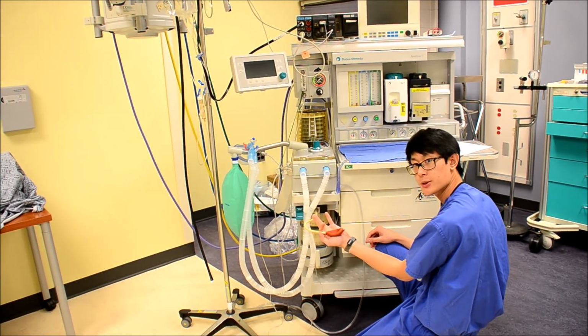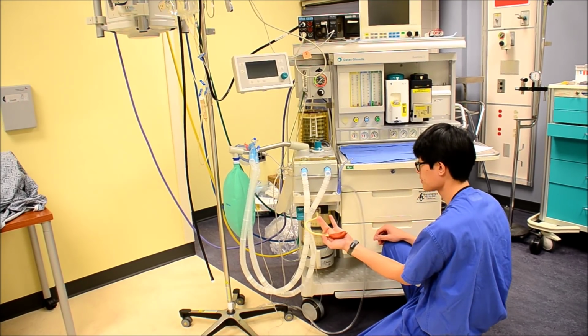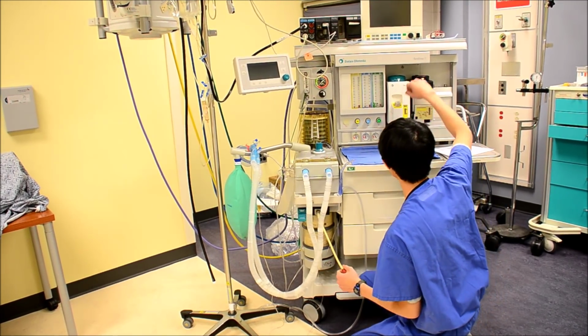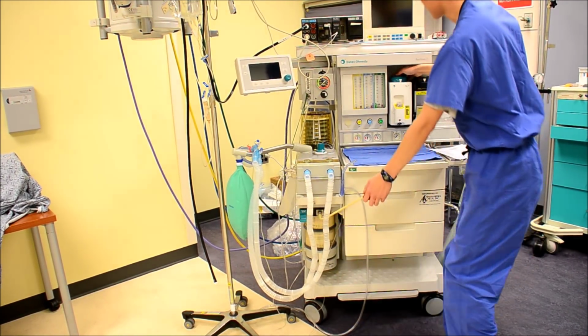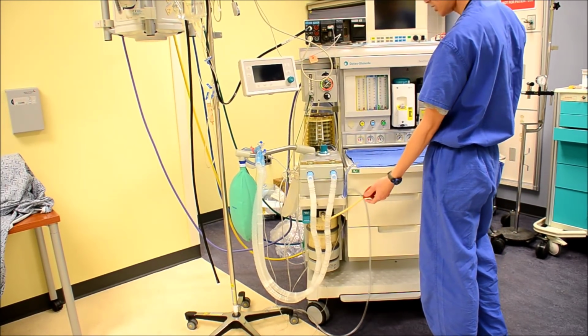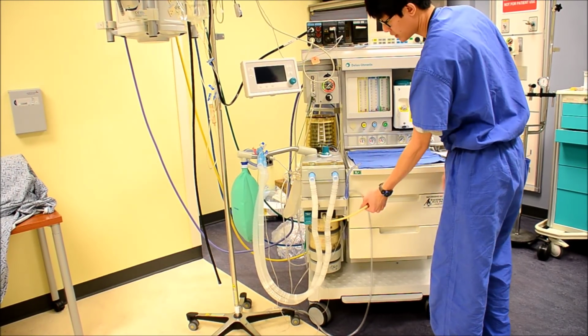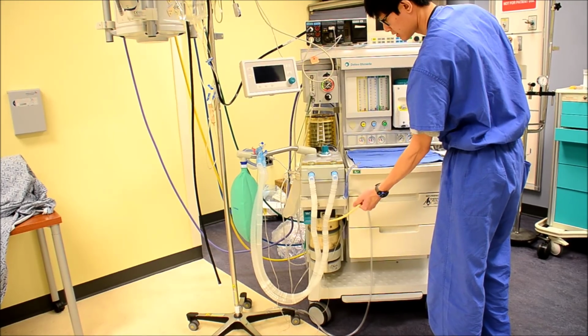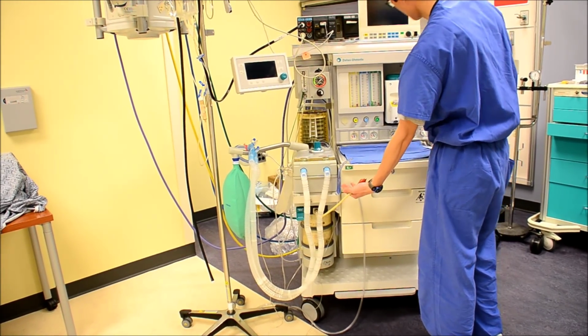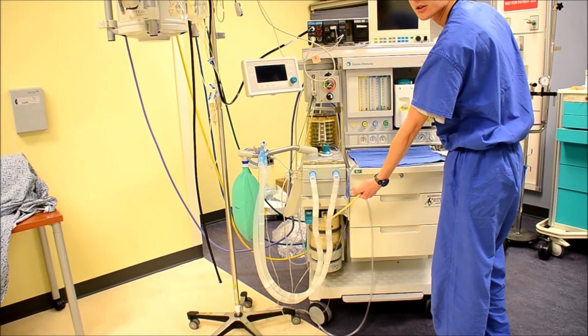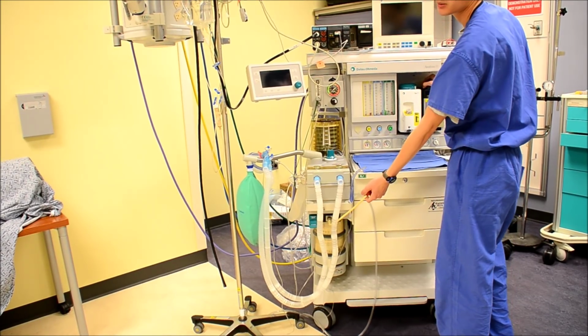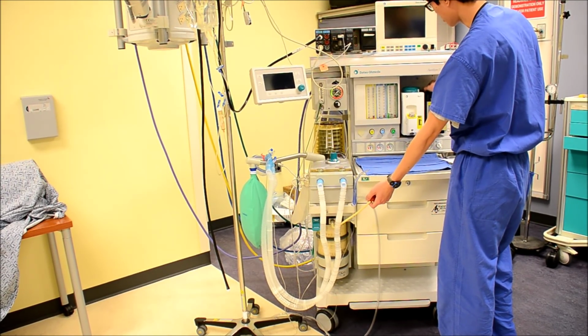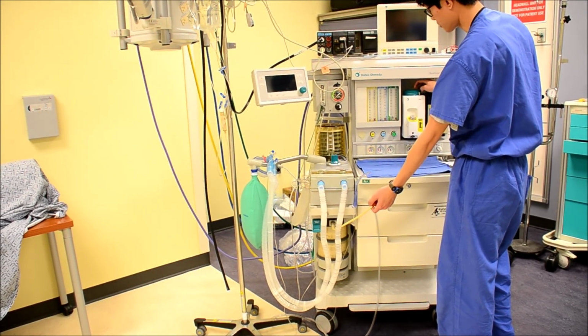Make sure it stays for 10 seconds as well. Once you've verified that, you'll go ahead and crack open one of your vaporizers. As you can tell, the bulb deflates, so we'll have to do it again for 10 seconds. And at this time, you can check your interlock system to make sure that's working. So I shouldn't be able to open the vaporizer next to this one if this one's already open.